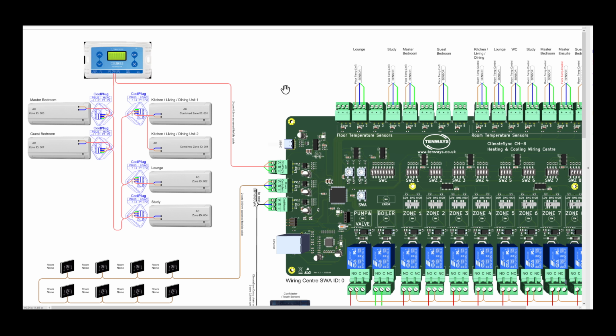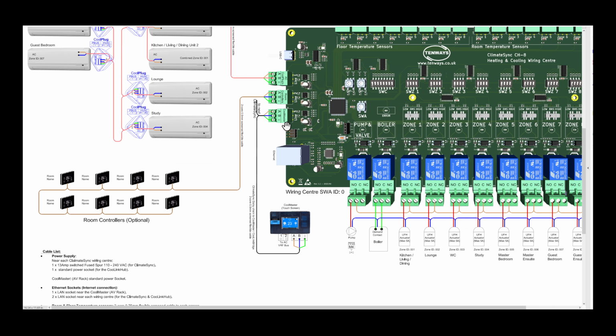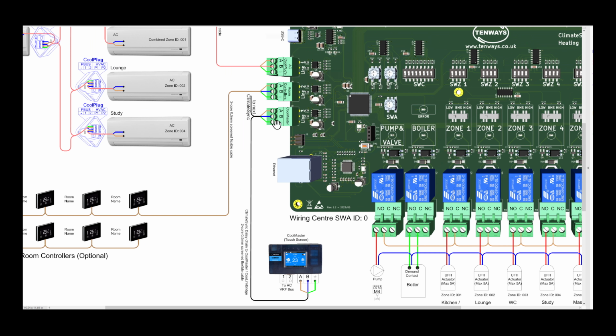So in a case where you're going to put the CoolPlugs by the indoor units, you do a daisy chain of a 2-core 0.5mm screened cable to all the indoor units, to all the plugs on the indoor units. And if you have the CoolPlugs by the wiring center, you're going to do the cable from the CoolPlug at the wiring center to each individual unit, a separate cable. Connection to the CoolMaster or cooling bridge will be a 2-core 0.5mm screened cable, which will go between all the wiring centers on line 3 back to the cooling bridge or CoolMaster.